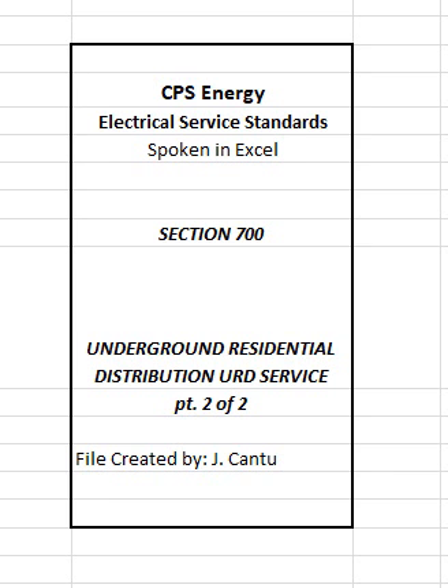704 Conduit connection to meter socket. Service lateral conduits typically are connected directly to meter sockets. Customer shall provide a 3-inch PVC male adapter for termination to both 200 and 320 ampere meter sockets. Exception 1. Where an auxiliary wire gutter or junction box is required by CPS Energy for multiple metering designs, refer to Figure 802 and Section 1800. Exception 2. Where instrument transformers are required by CPS Energy to supply larger residential loads, refer to Section 1800.